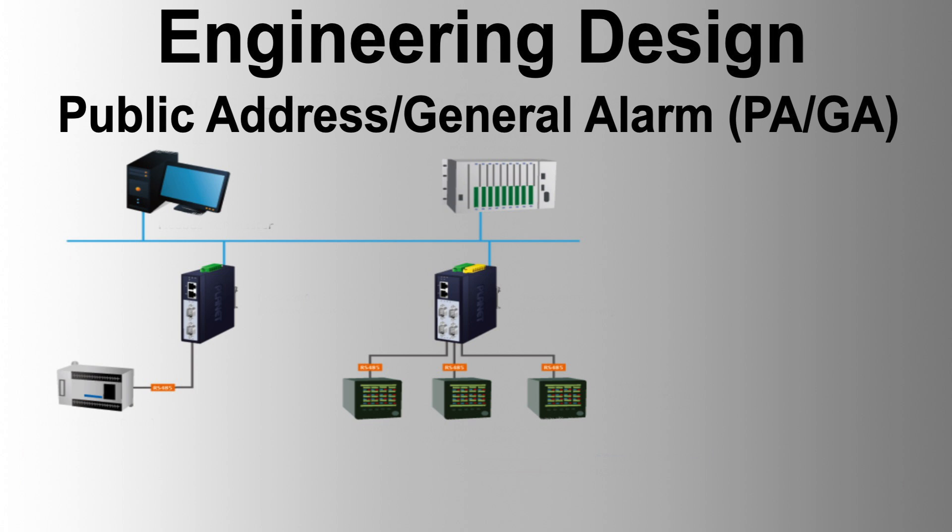PAGA loop design: system cabling is in a monitored loop design with status signals sent to the remote control room. Cables are laid separately for redundancy, minimizing the effects of cuts or shorts. Amplifiers and critical subsystems are in N+1 redundant configuration with automatic switching.